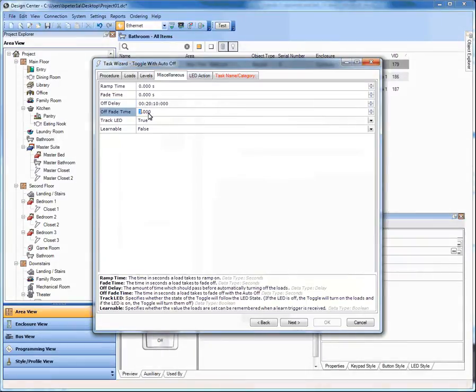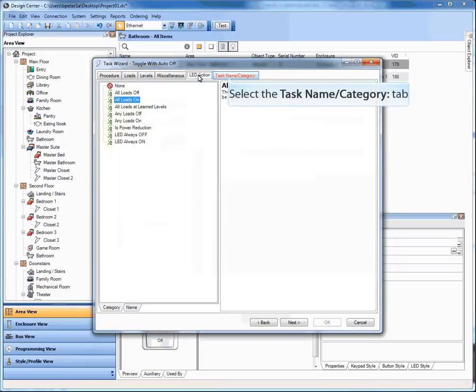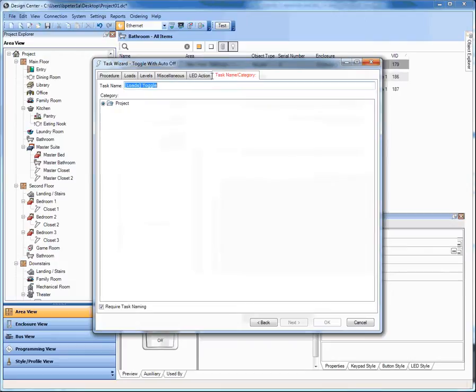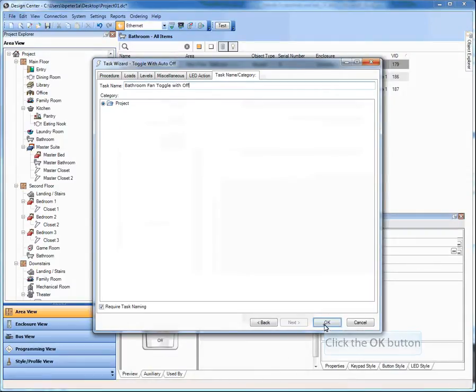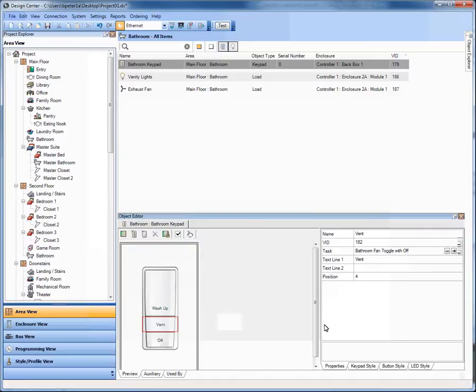Then I'm going to change my off fade time to zero as well. My LED action I'll set to all loads on, meaning if the exhaust fan is on the LED will be on. And then I can give it a name. In this case I'm just going to call it the bathroom fan toggle with off. And I click OK. It's as simple and straightforward as that. Now I've just created an auto off without having to go back in and create some additional lines of code for the delay and the off. Pretty cool.